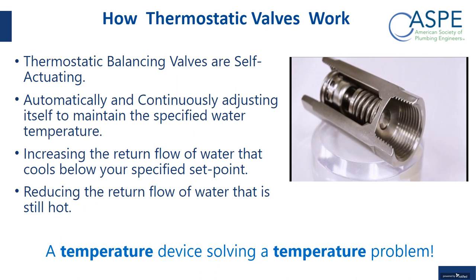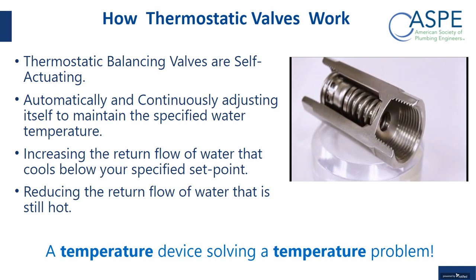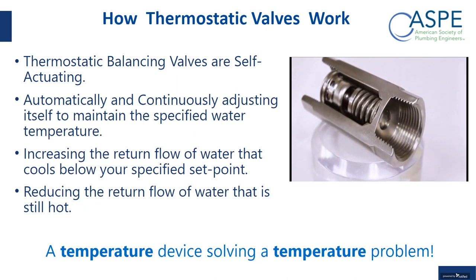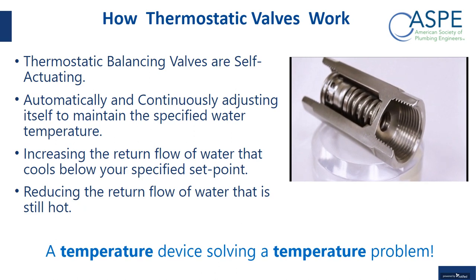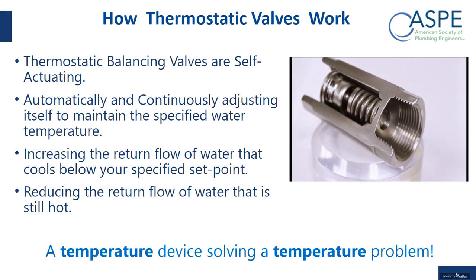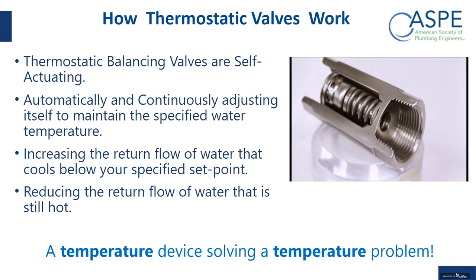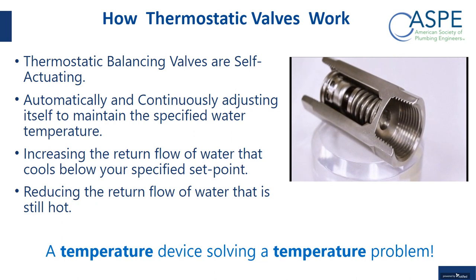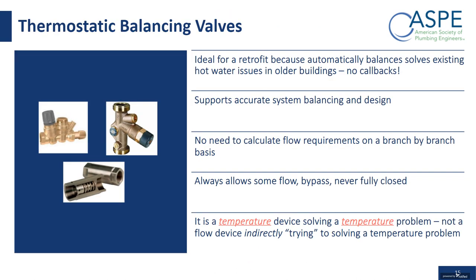What I always like to say, and you may hear me say several more times in this presentation, is this is a temperature device solving a temperature problem. Unlike the manual balancing valve and the pressure independent valves, which are both flow devices trying to indirectly figure out what flow rate you need to offset the heat loss in the system, these are directly solving the problem because they're temperature devices.